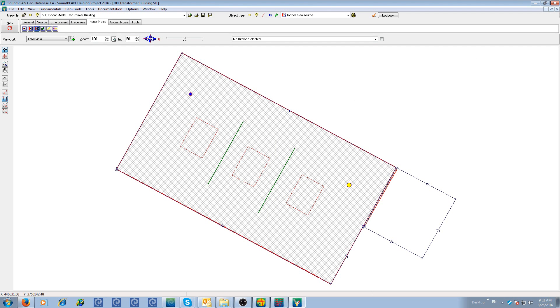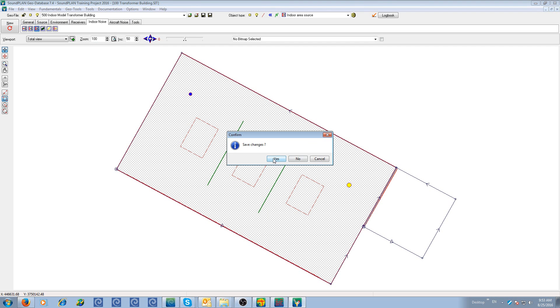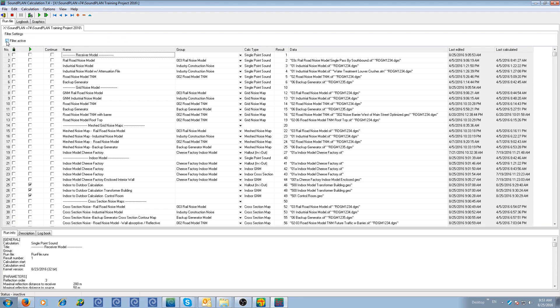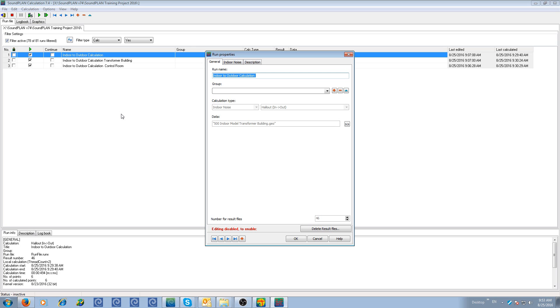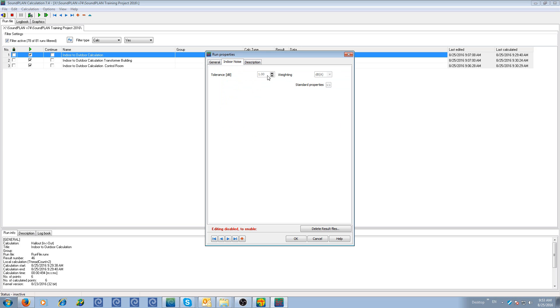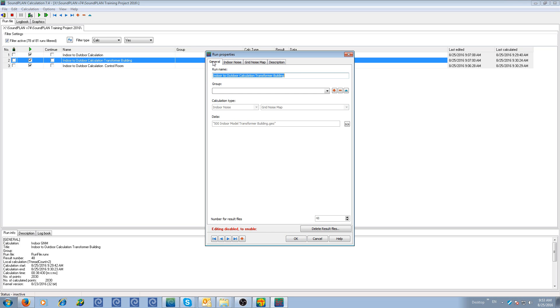Let me exit out of the geodatabase and we'll talk about the calculation. So here is the calculation parameters. I'm filtering, I'm only looking at the ones that we will run. The first one is a hall out calculation. This will calculate the levels inside the transformer room on the inside of the facades and any insides of area sources that we defined, like the doors and windows. We have the geofile, indoor parameter calculations, the tolerance, and the frequency weighting.